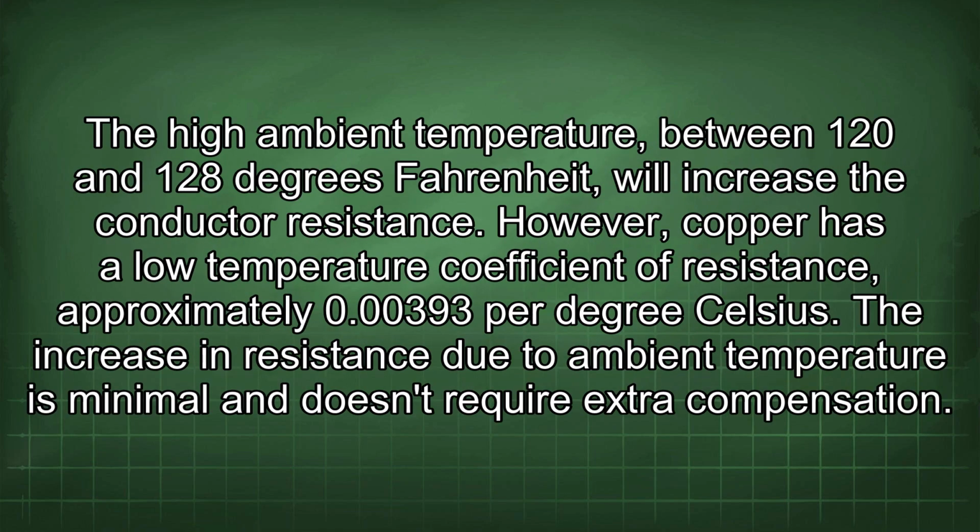The high ambient temperature, between 120 and 128 degrees Fahrenheit, will increase the conductor resistance. However, copper has a low temperature coefficient of resistance, approximately 0.00393 per degree Celsius. The increase in resistance due to ambient temperature is minimal and doesn't require extra compensation.